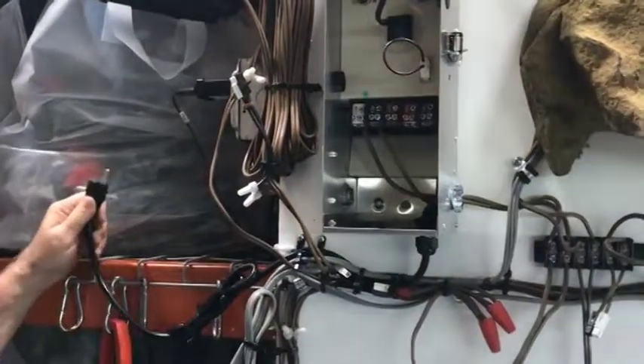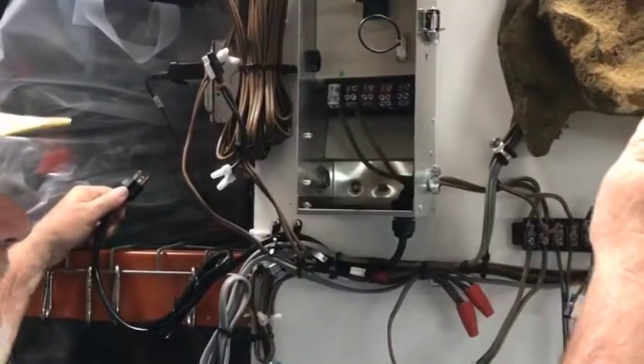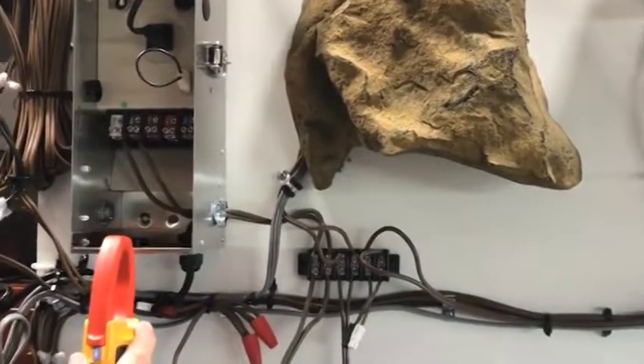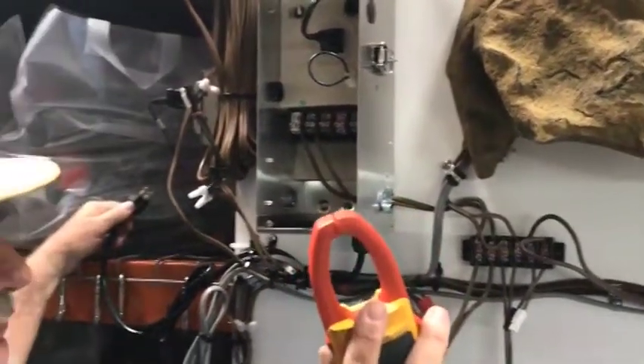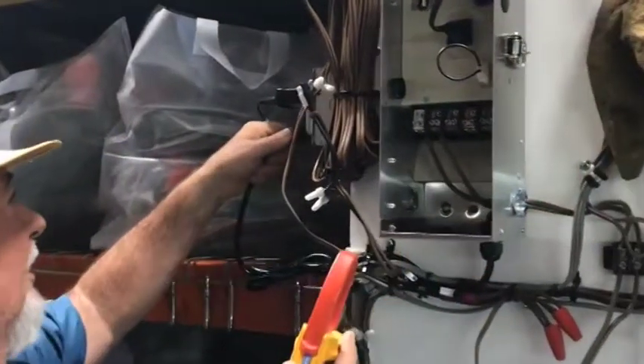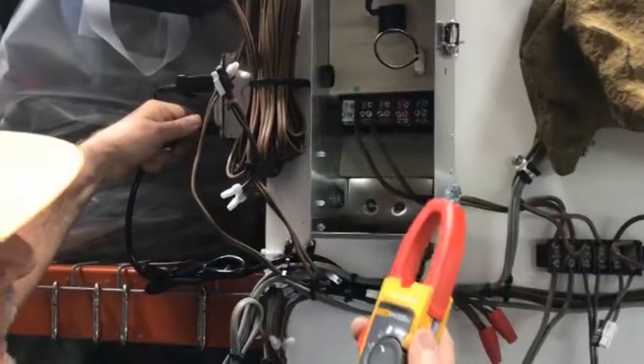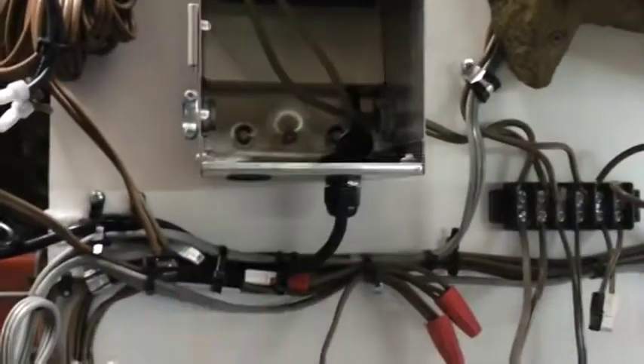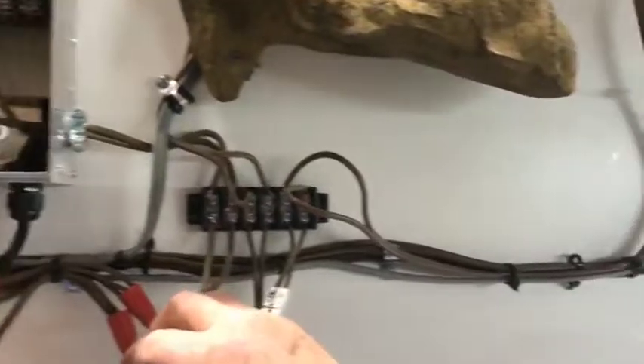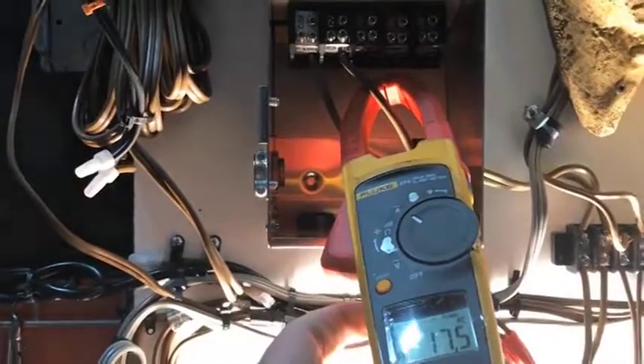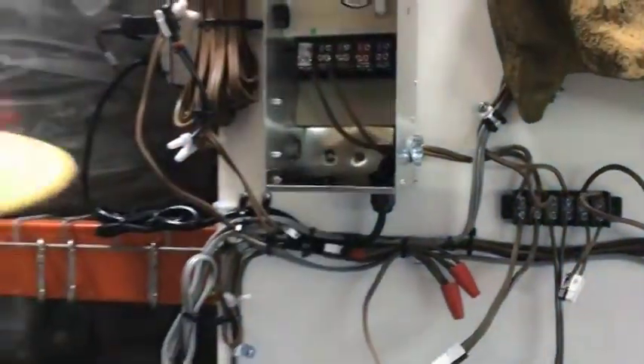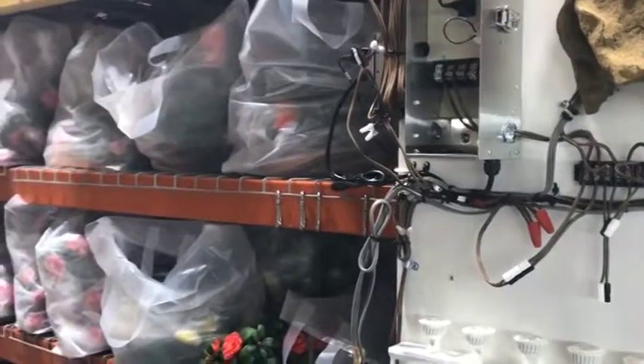And we're going to hook up a traditional 150 watt transformer. I'm going to have to get my amp probe ready. The 150 watt transformer, 150 watt transformer, they are not equal. They don't look equal. This is like rock, paper, scissors. Rock always wins. All right, so here we go. I'm going to put it on the secondary fast. Try to hook it up. 17.5, and it tripped. Of course it tripped. It's the advantage of having secondary protection.